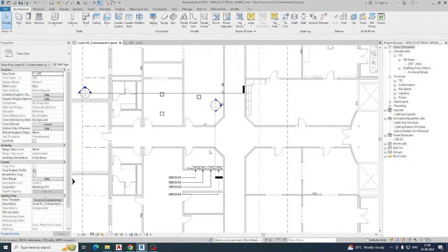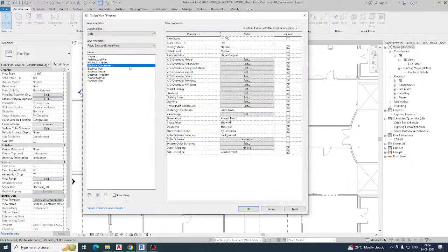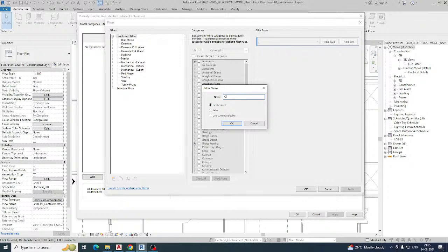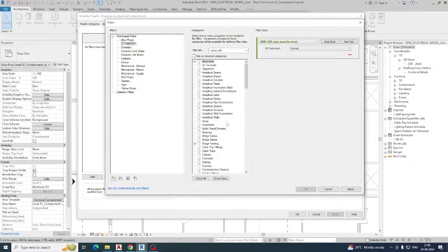For example, this is the riser — I need to run the cable tray from here to over there. First, I need to create some filters. Go to the containment view template, then go to filters, then go to Edit/New. I need to create some filters first. For example, a cable tray for SMDB-01. Select the categories — cable tray and cable tray fitting — from here.